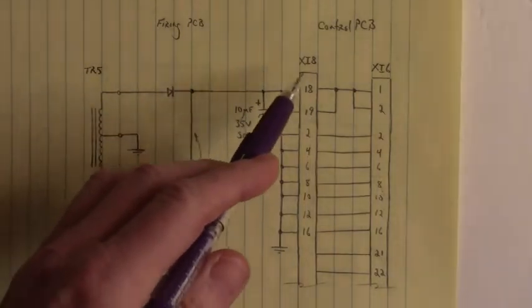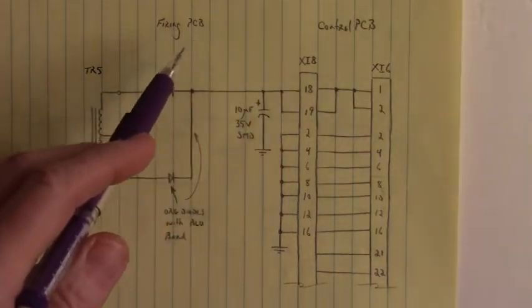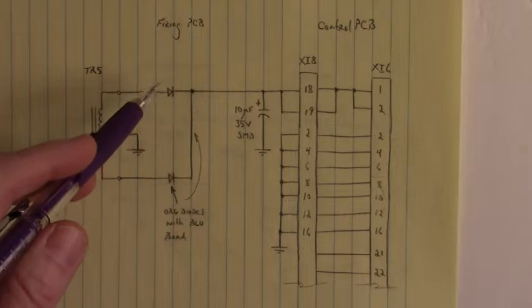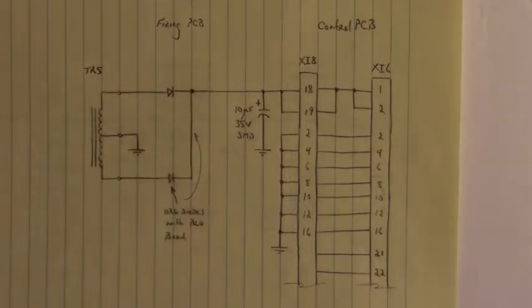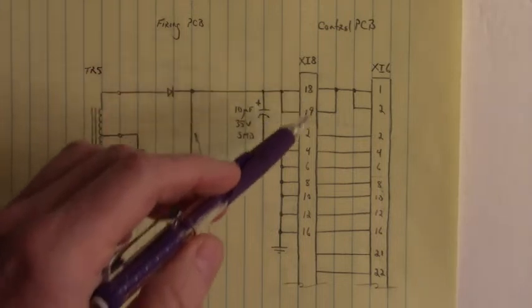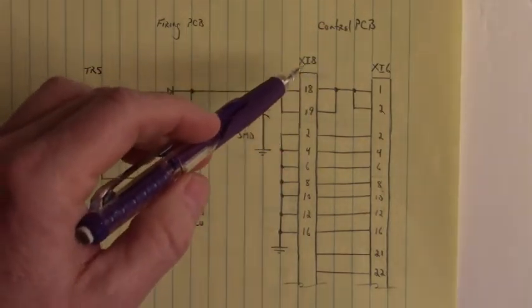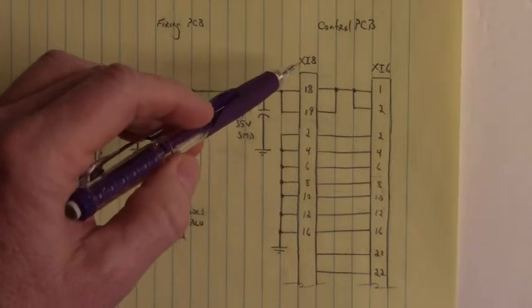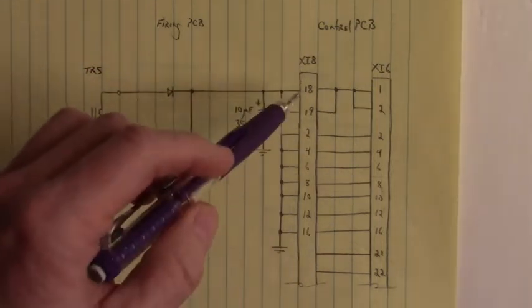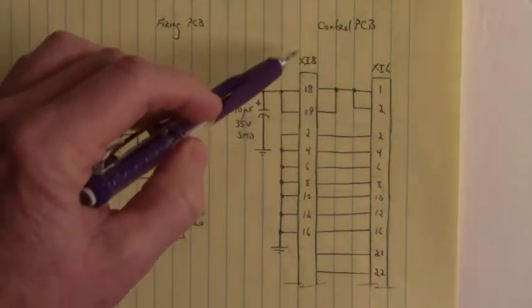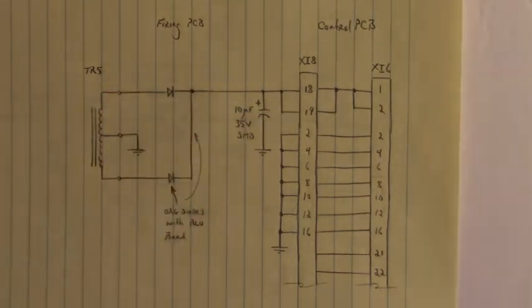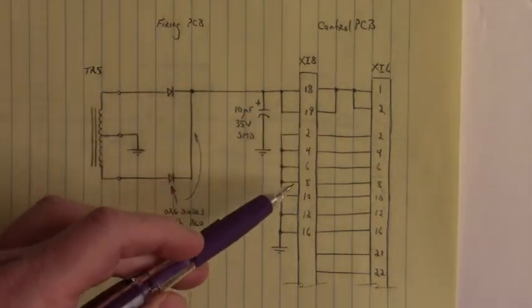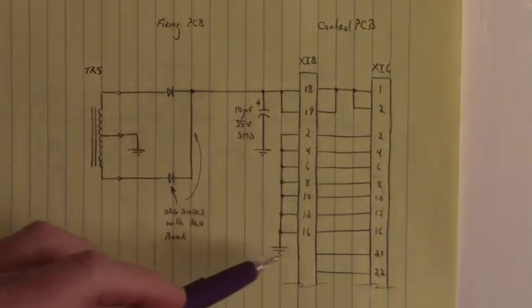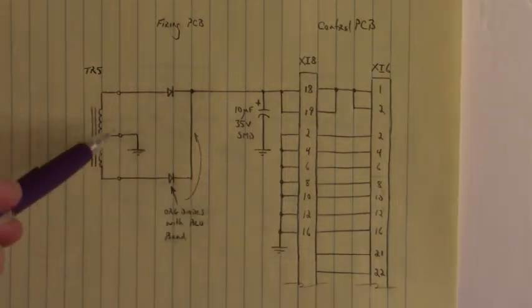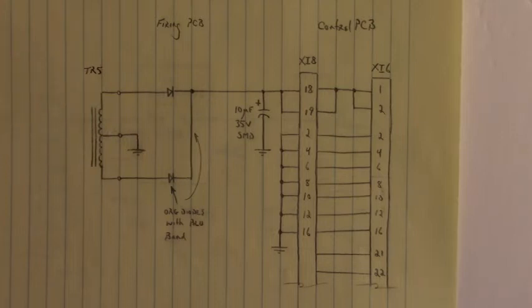Now look, we go from the firing board where this transformer, 2 diodes, filter capacitor reside, up to the control board. And here we have a ribbon cable. It's called XI8. On the control board, it comes in on XI8, pins 18, 19. Here's ground, 2, 4, 6, 8, 10, 12, and 16. This is the same ground back to the center tap of the TR5 transformer.